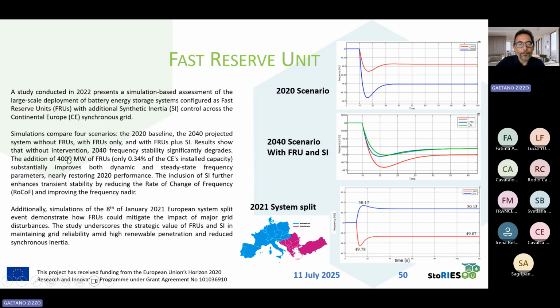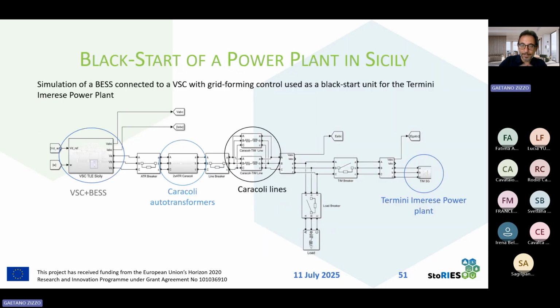If we are able to install 4 gigawatts of fast reserve units from now to 2040, the performance of the power system of the continental Europe synchronous area will not vary in a significant way, and the same security that we have now could be maintained in the next 20 years. We have also applied the use of the fast reserve unit in a real case, the system split that happened on the 8th of January 2021, and we have demonstrated that thanks to the fast reserve units, if they had been implemented in all Europe, the system split would not have occurred, and Europe would be a single area for all time.